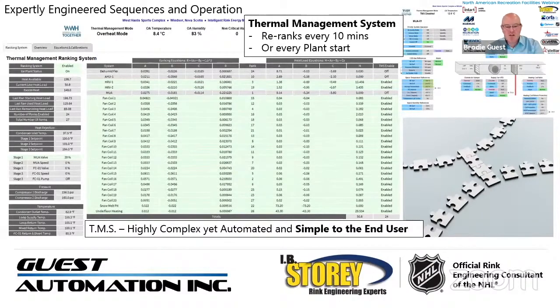On the top banner of that same screenshot, we see the TMS mode is currently in overheat mode. So again, since the building is almost satisfied, we're taking our excess heat and temporarily increasing each zone set point by 2 degrees Celsius, which allows these zones to coast back down to their normal set point when the plant turns off.